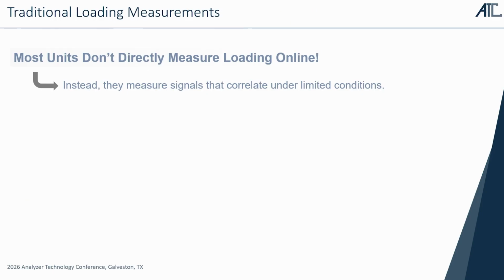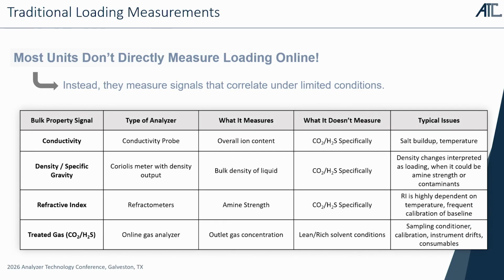So traditionally, in today's world, most amine units don't actually directly measure loading online. Instead, they measure signals that correlate under limited conditions. So they are really looking at bulk property signals like conductivities, densities of the rich and lean amines, refractive indexes with refractometers, treated gas analyzers, things like that. And each of these is really good at the narrow area that it measures, but they also come with cons, as all analyzers do, of course. But what if we could do something that does all of this together, instead of having individual analyzers that aren't really even doing things online in an unlimited way?